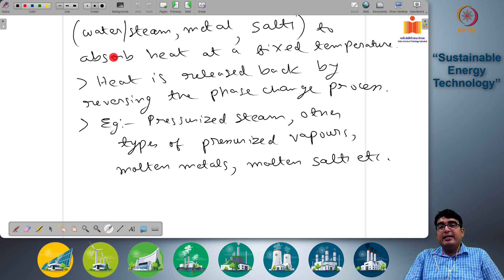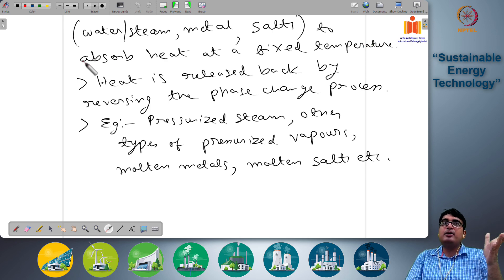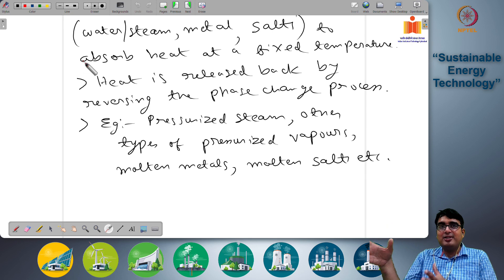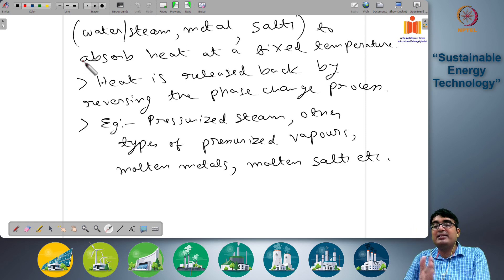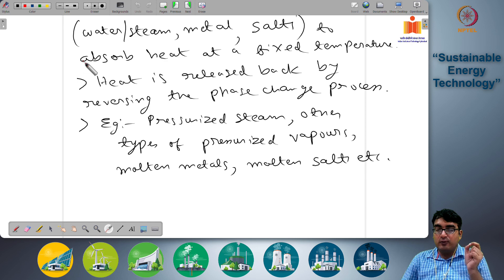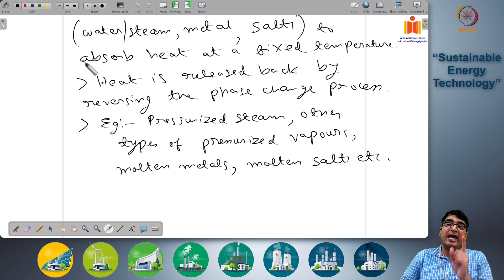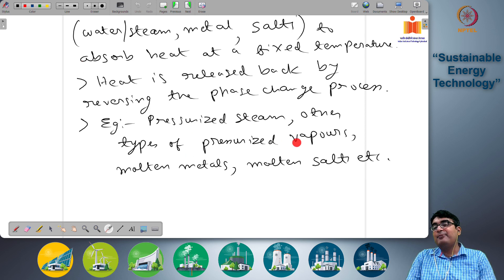The advantage of phase change materials is that heat is absorbed and released at a fixed temperature. This is very important because many industrial processes require heat transfer at a fixed temperature, and many energy systems need a fixed temperature for high-efficiency electricity production. When the temperature of heat transfer needs to be in a narrow band, phase change materials are very useful — when a substance is changing phase it does not change its temperature, so you get heat transfer at a fixed temperature. Options include pressurized steam, other pressurized vapors, molten metals, and molten salts.